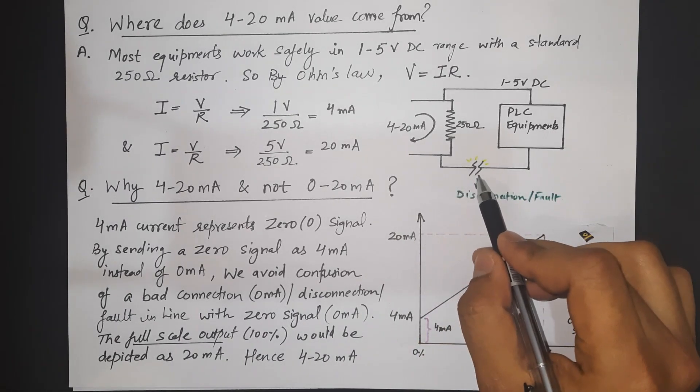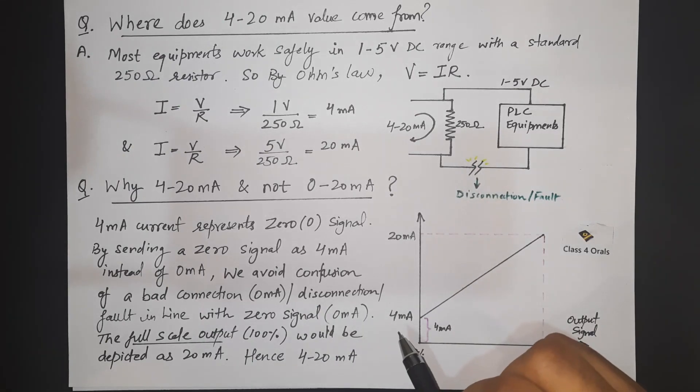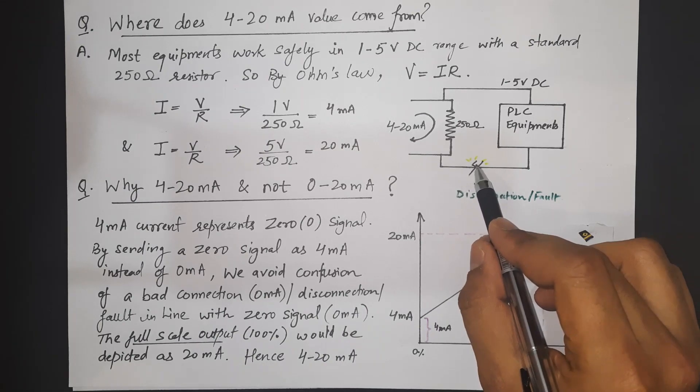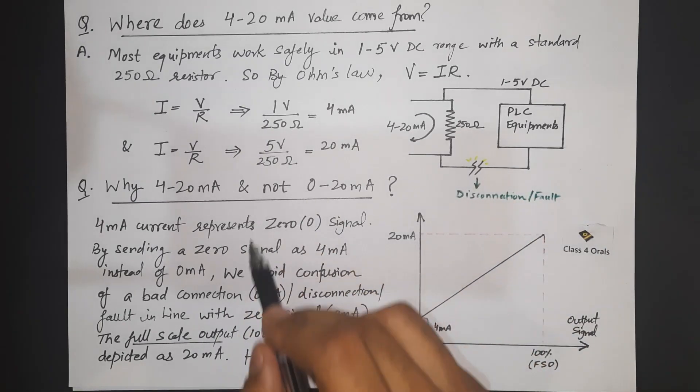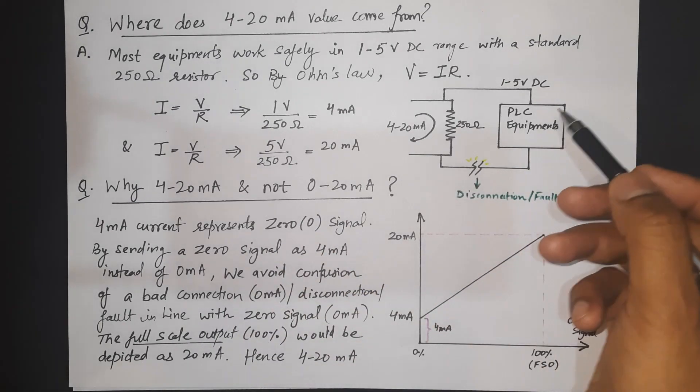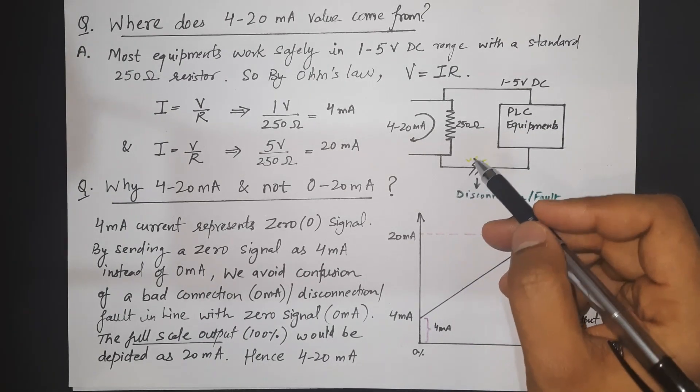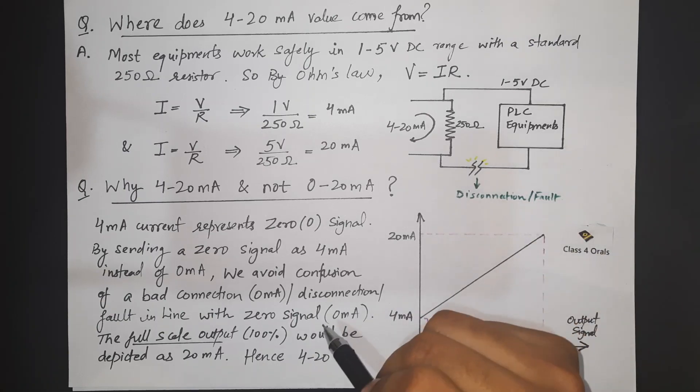If there is some disconnection that means there is no current or there is no output going. So if we are measuring with 0 mA you will not get to know whether the system is having any kind of breakage or not or any disconnection or not.